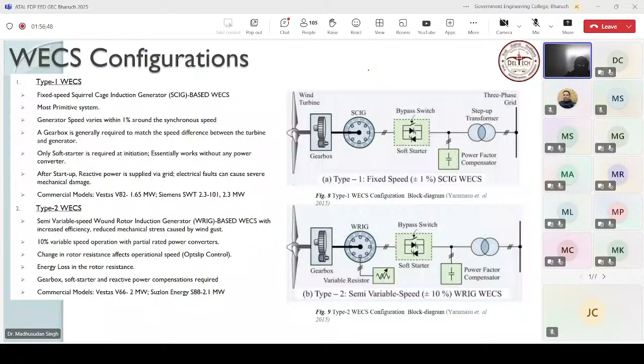Type 1 arrangement is almost a fixed speed operation. You see, fixed speed means the variation in speed is just 1% here, whereas here you see it is just 10%. So these type 2 based machines are being manufactured by Suzlon Energy up to a capacity of 2 megawatt, very common and commercially available. With this, Vestas also has a 2 megawatt such arrangement where you have turbine and wound rotor induction generators.